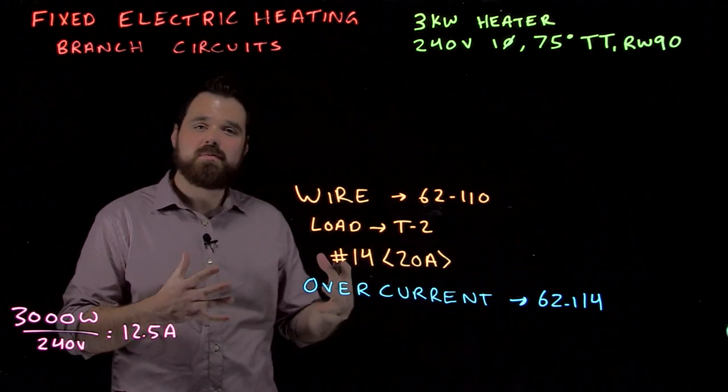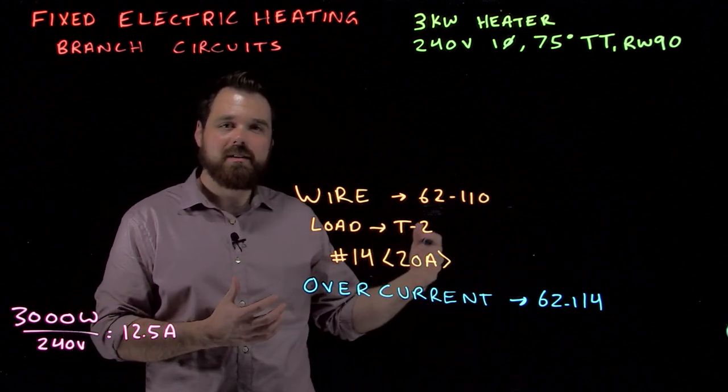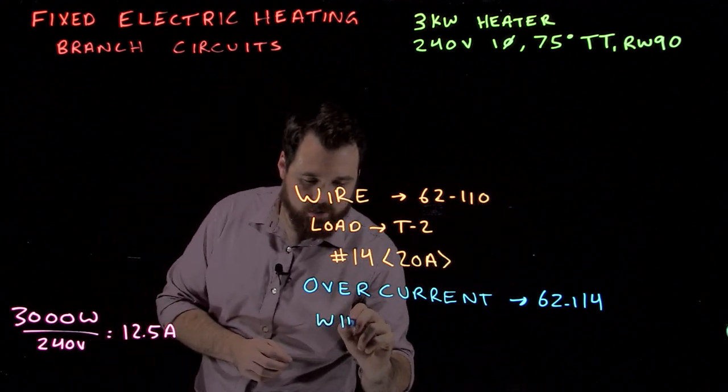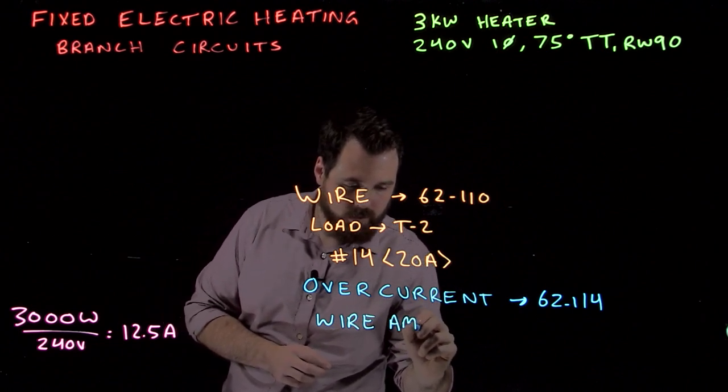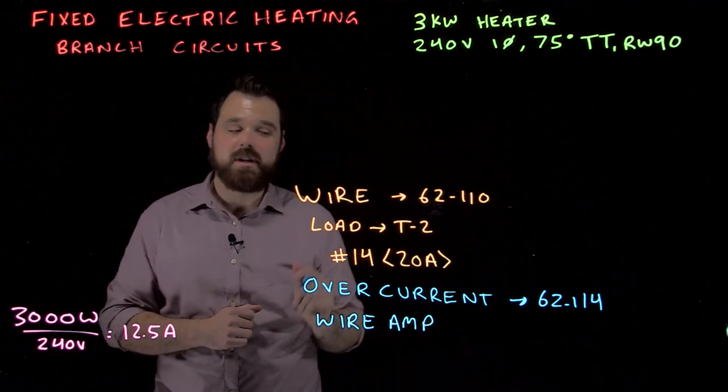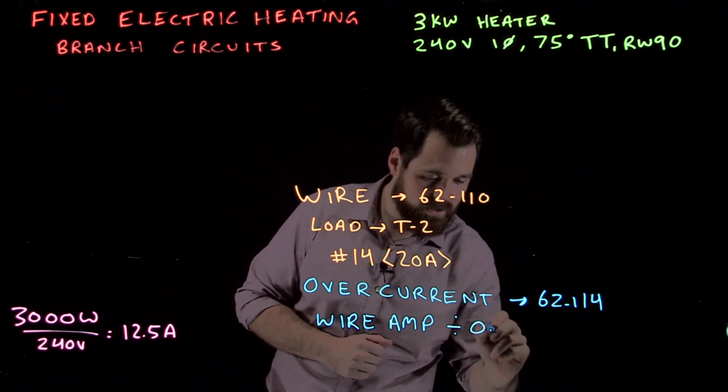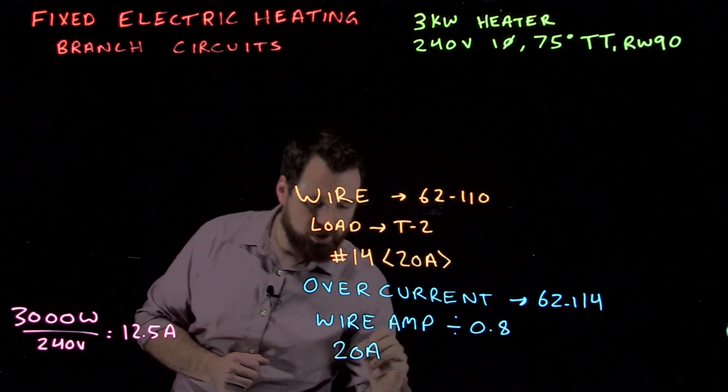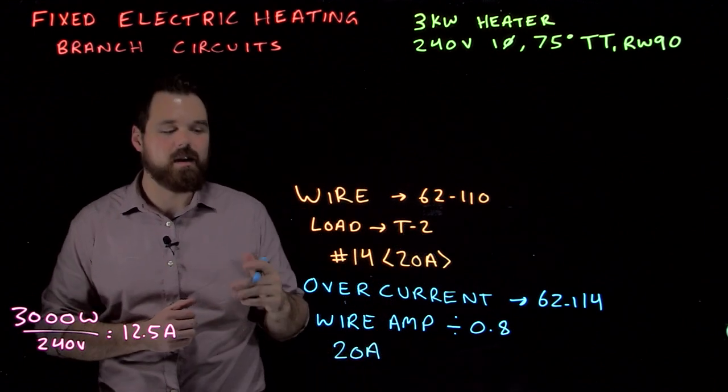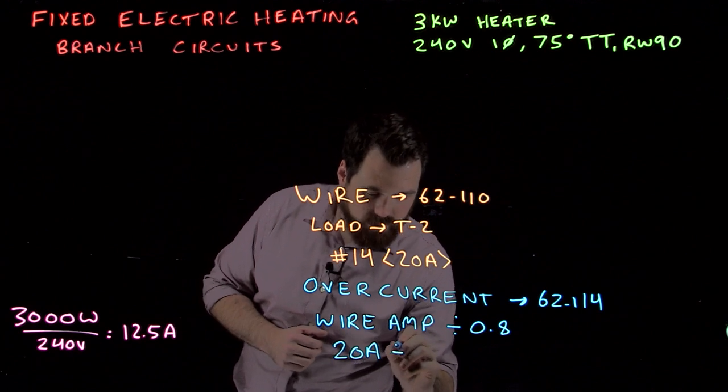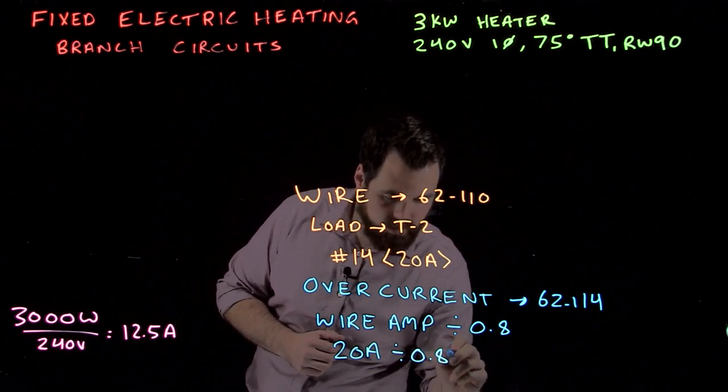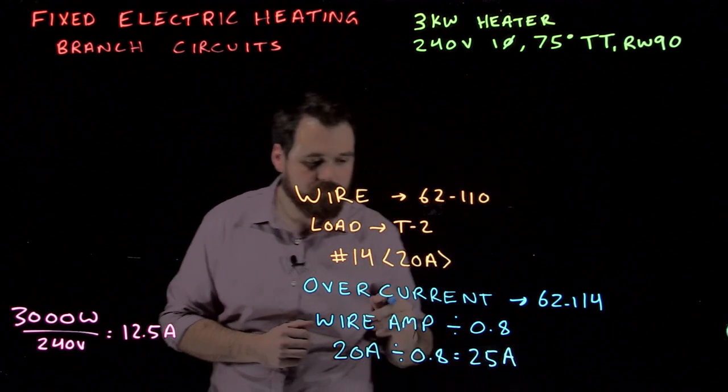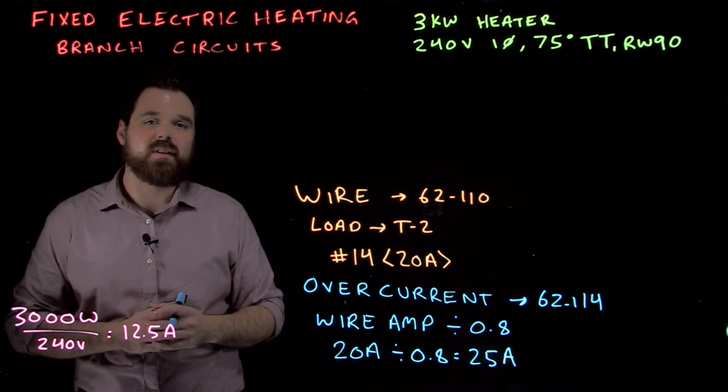So what this means is because the allowable ampacity of our wire cannot exceed 80%, what we do is we take the wire ampacity, which we got from table 2, and we divide by 0.8. So we go 20 amps, which is the allowable ampacity of our wire. We divide by 0.8 and that gives us 25 amps. So our breaker can be a 25 amp breaker.